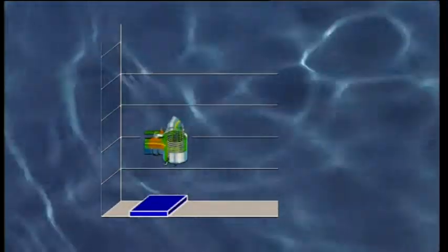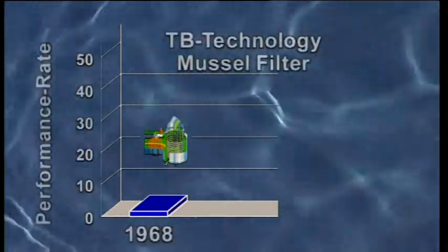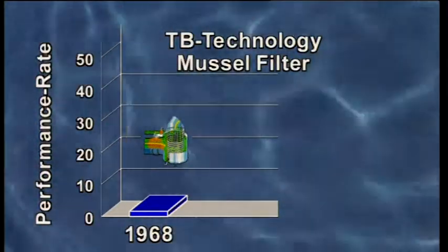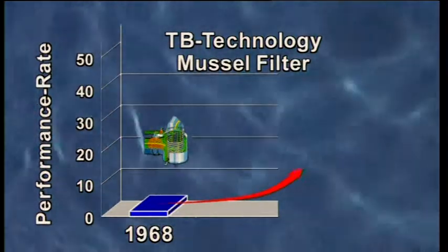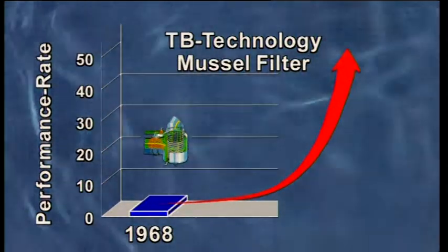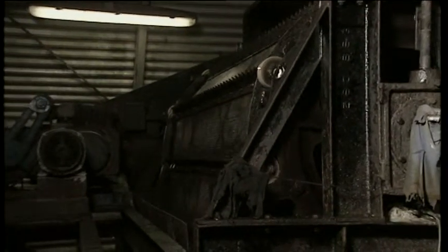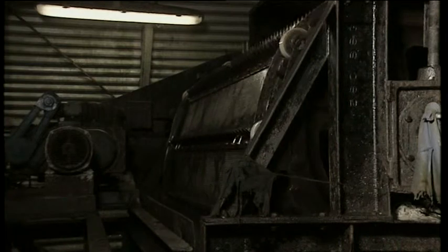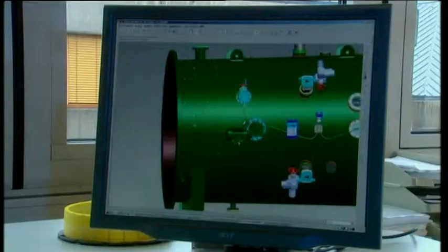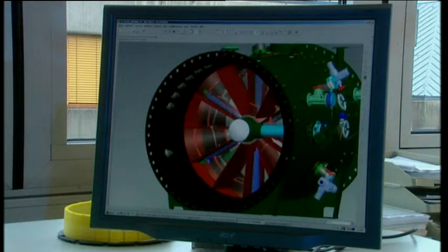What fundamental economies could be achieved at the pre-screening systems, meaning upstream of the cooling water pumps, if the performance of the filters was increased even further? Particularly, the technically obsolete and maintenance-intensive travelling band screens could be done away with completely, given the fact that the existing rakes provide sufficient pump protection. This consideration resulted in the development of the Taprogge high-performance filters.